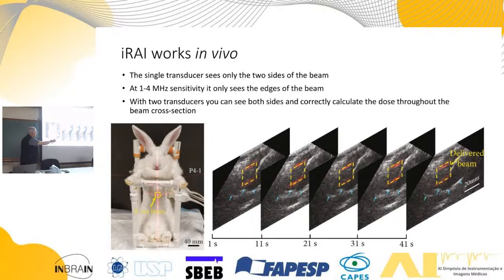But your ultrasound frequency is pretty high. This, I think, was an average 2.5 megahertz array. So a wavelength is probably about that kind of distance, and so you're only seeing the edges. But if you know about what the shape of the beam is, you can fill in and get quantitative with what the radiation dose was, as well as whether it was in the right place in the first place. This is a safety check, another check that you're delivering the dose to the right place in the body.